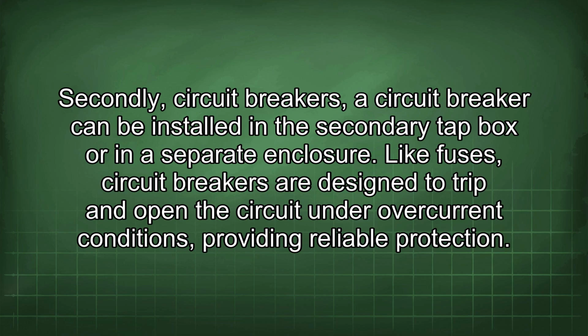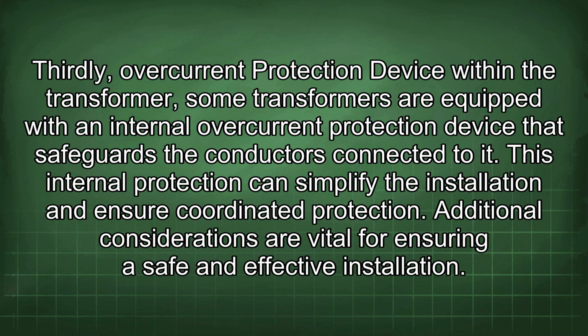A circuit breaker can be installed in the secondary tap box or in a separate enclosure. Like fuses, circuit breakers are designed to trip and open the circuit under overcurrent conditions, providing reliable protection. Thirdly, overcurrent protection device within the transformer. Some transformers are equipped with an internal overcurrent protection device that safeguards the conductors connected to it. This internal protection can simplify the installation and ensure coordinated protection.